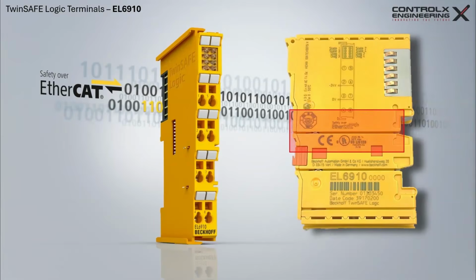Here you can see all the conformity markings. For the North American market, the CUL US is an important marking, which means that the product has been tested and certified by UL to meet both US and Canadian safety standards. In other words, a device with the CUL US mark has passed recognized safety testing for electrical equipment in both countries, giving engineers and inspectors confidence that it meets the required safety and performance standards.